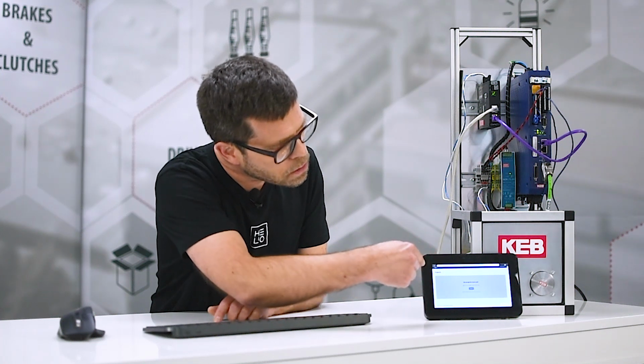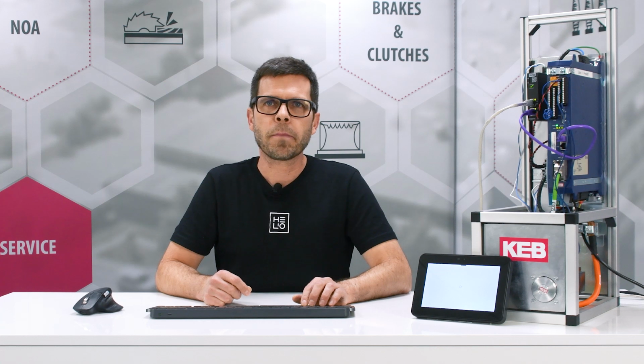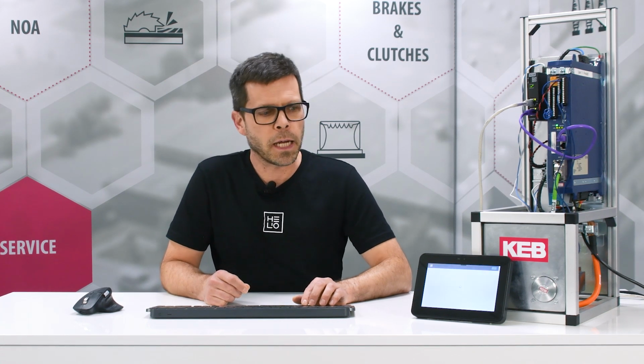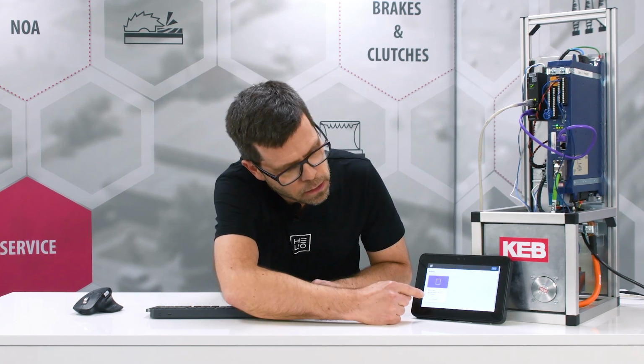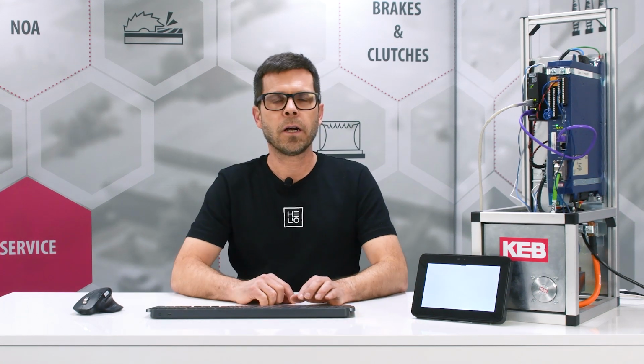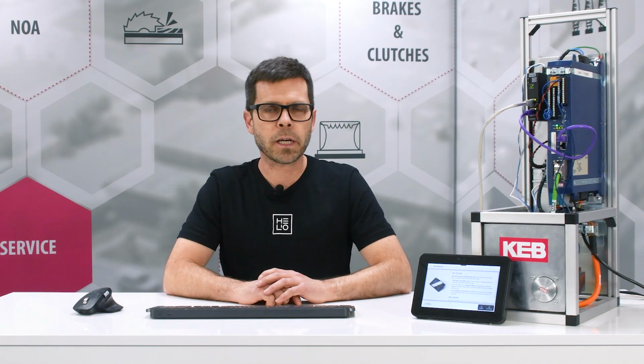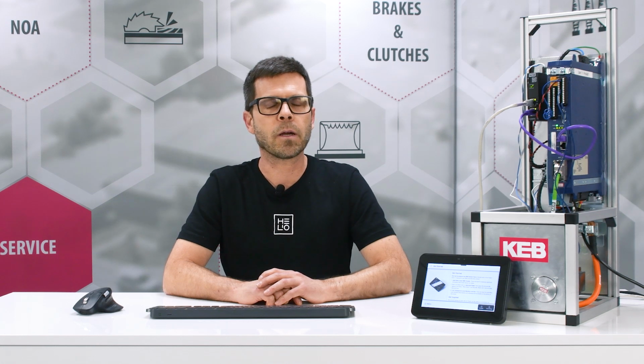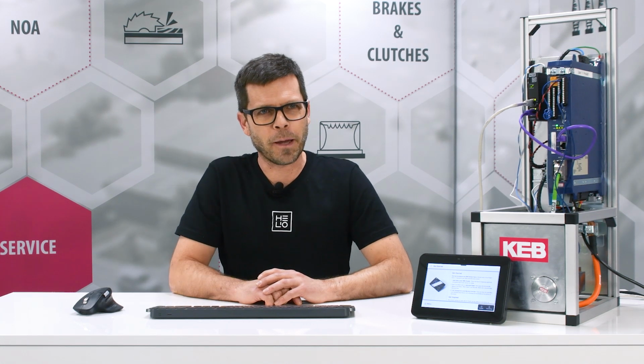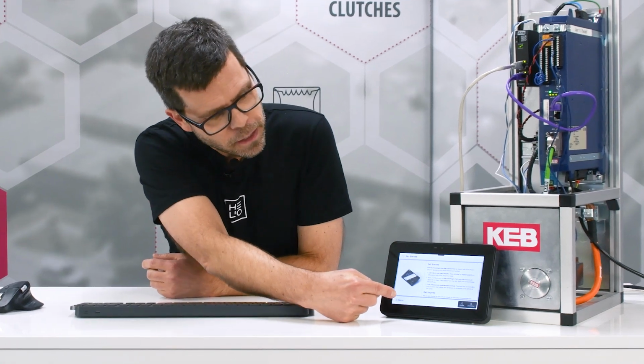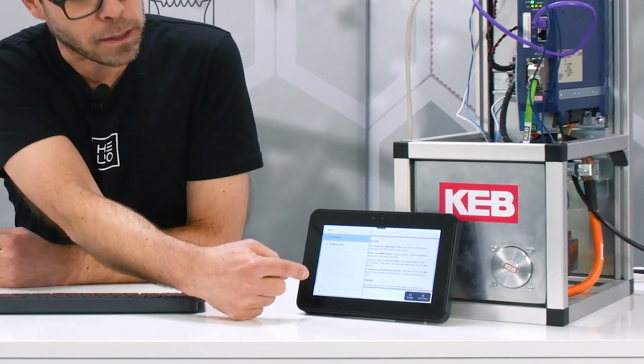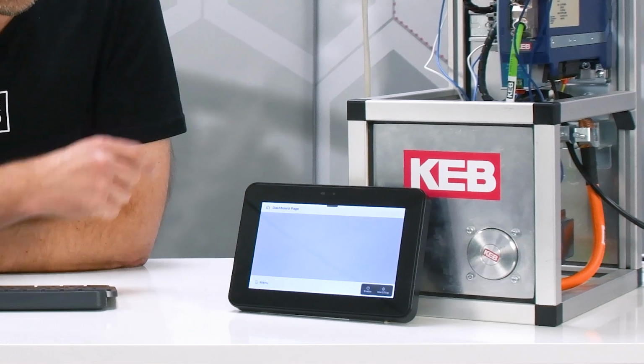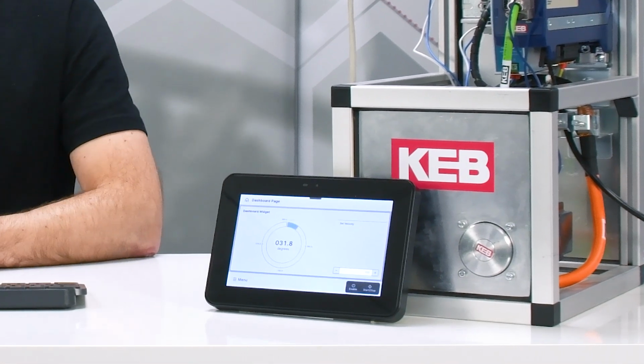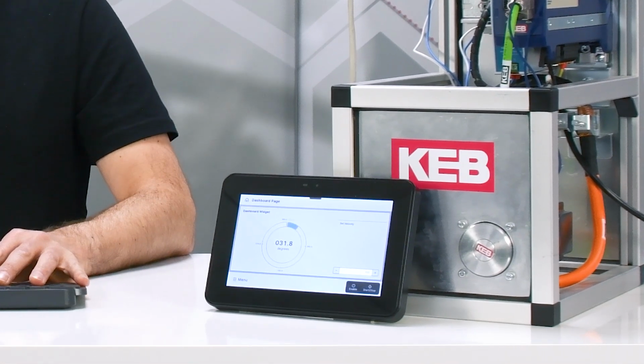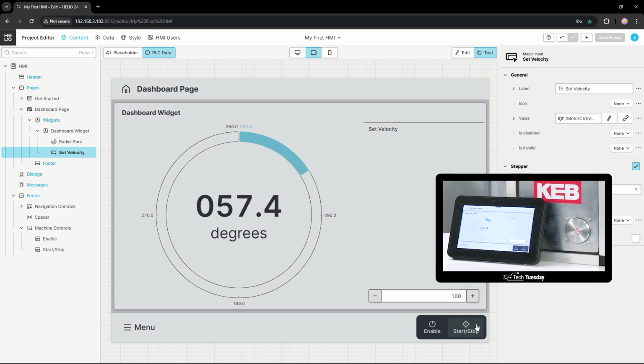I hope this works. Oh yeah. And now it shows us our freshly created my first HMI project that I can run on the actual panel without logging in. I see the first screen from the empty HMI, and what we get is the main navigation since we created a second page. I can switch to that one, and you see here that everything is working.